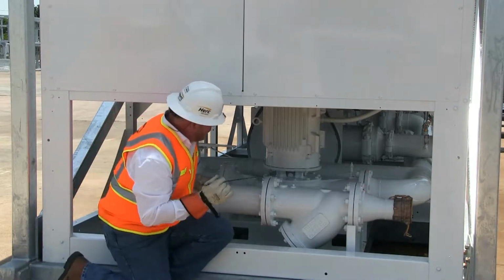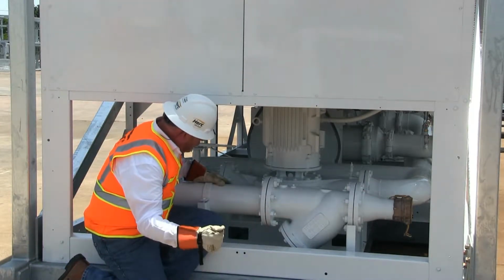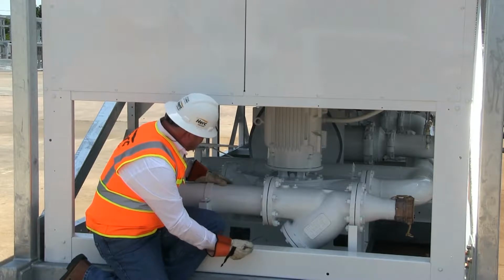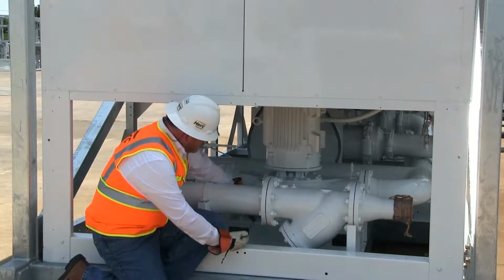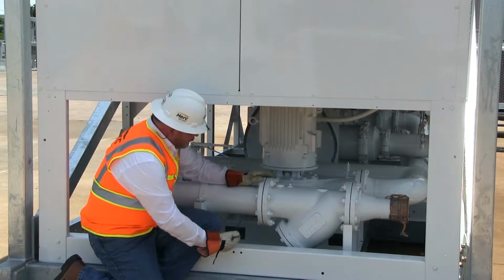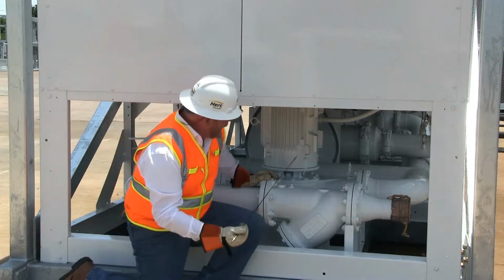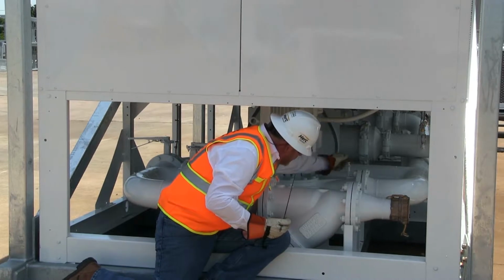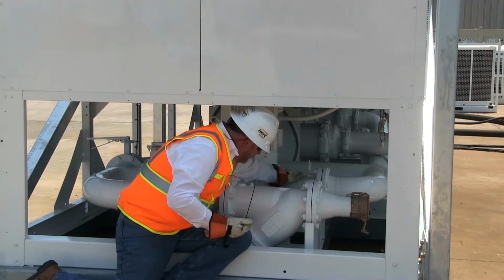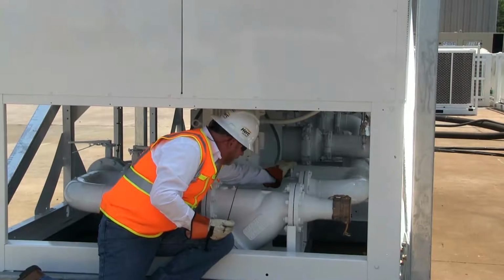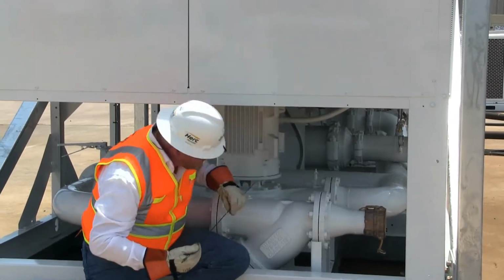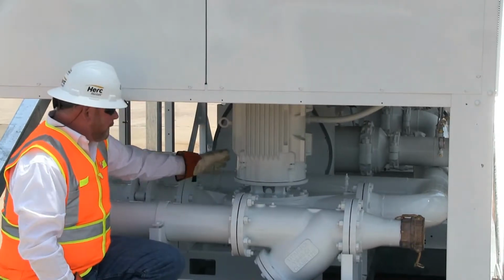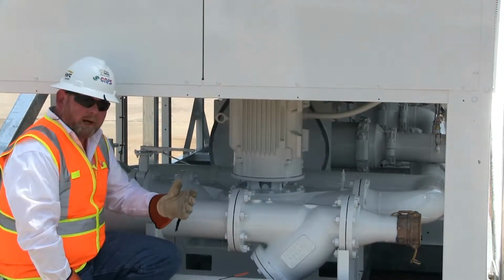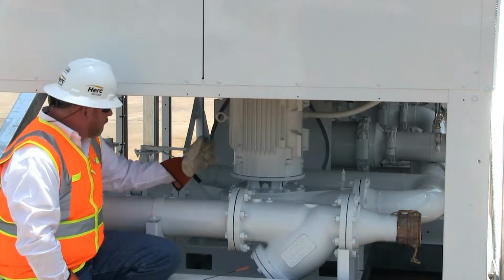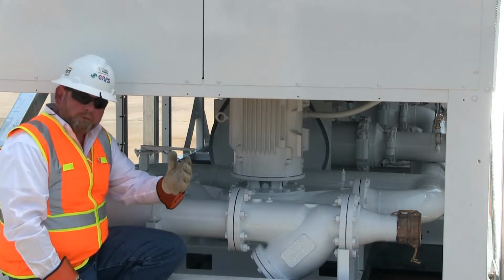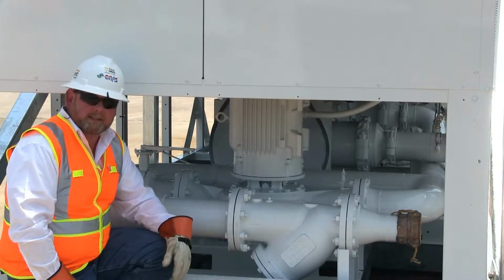A few other items I want to point out here is the main bottom drain for winterization is right here under the bottom of the volute of the pump. There's a ball valve there that you can drain the water out of the pump casting during winterization or cold storage. And then the last item is right here is a T-valve at the top. We're going to open that up to bleed air out of the pump so we get a good prime on the pump itself. So your decisions here are just going to be to ask the client if we're going to use our pump on board to circulate water through the process or the comfort cooling application, or if we're going to block ours out and use their pump. Both are acceptable as long as it's sized for the size of the 200-ton machine.